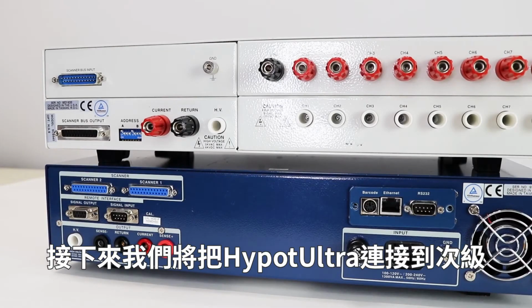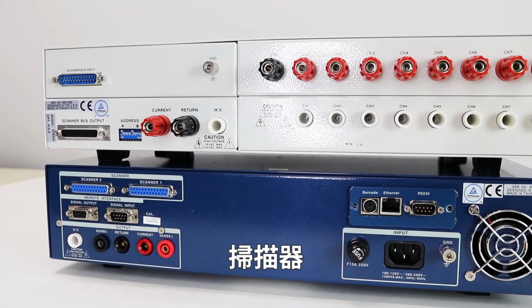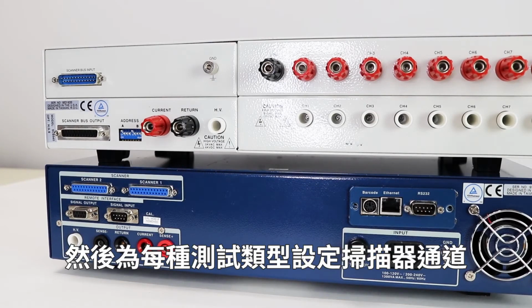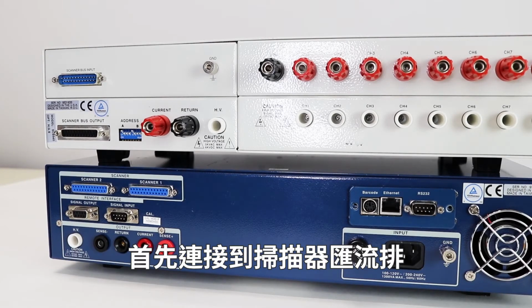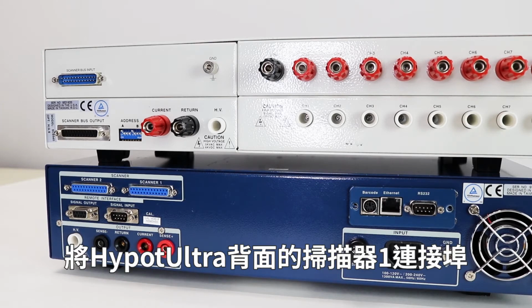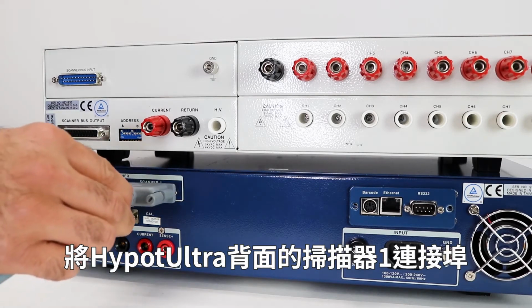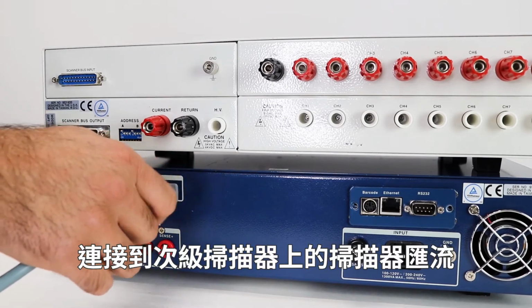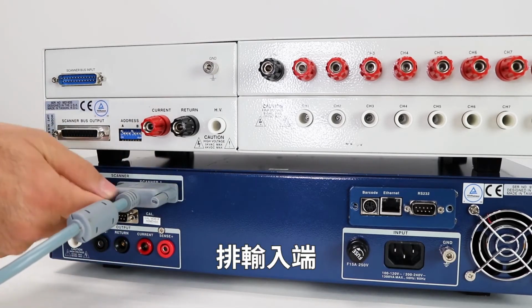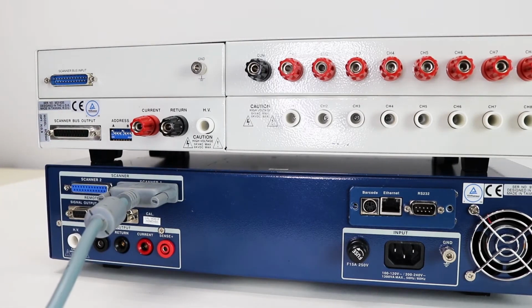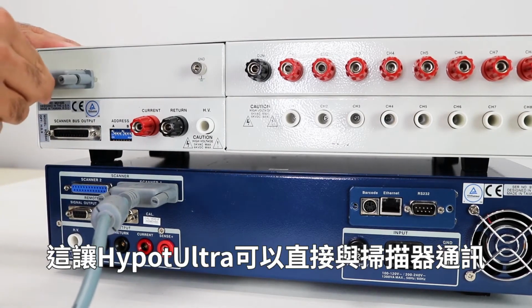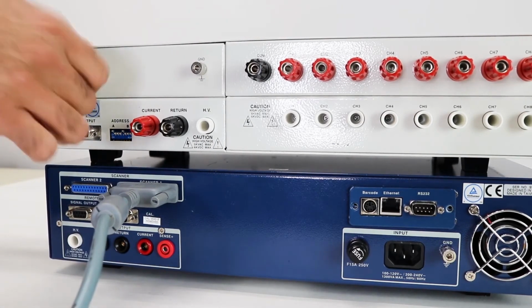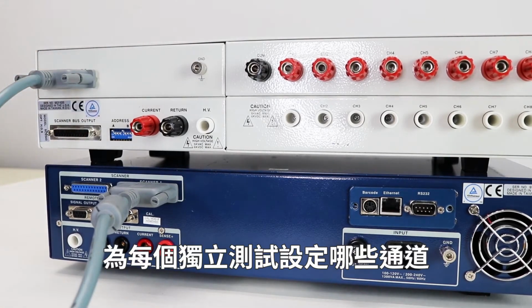Next, we're going to connect the HypotULTRA to a secondary scanner, then set up the scanner channels for each type of test. First, connect to the scanner bus. Connect the scanner 1 port on the back of the HypotULTRA to the scanner bus input on the secondary scanner. Use the screws to tighten the connection.